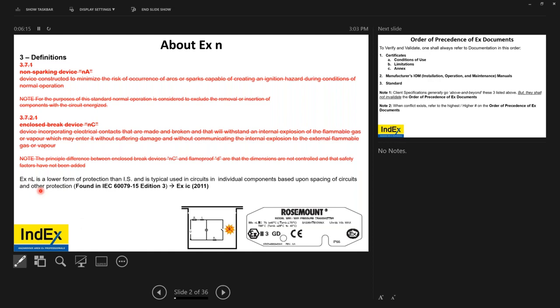So EXNL is a lower form of protection than intrinsically safe. Actually, what it is, EXIC. Zero faults allowed. So it's feeding a circuit. The barrier obviously would have to be inside of a substation or within a junction box, feeding a specific cable. Energy limiting cable going to an energy limiting device.